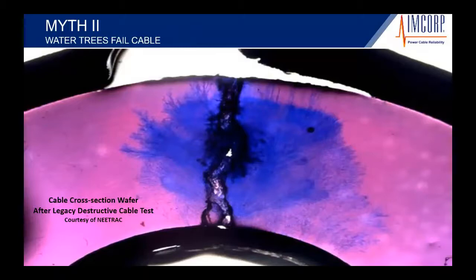We always see water trees. They're not very hard to find. It's the carbon tree, the carbon path, that's the most difficult. Typically, when these go to failure, it's pretty catastrophic and you don't have a whole lot of evidence. But when a water tree is combined with some sort of void, a manufacturer's defect in the cable, an installation defect or some contamination, that combination can cause a carbon path to develop and go to failure. It goes from your inner conductor, which is the strand shield, to the outer conductor, which is that semiconductive material.